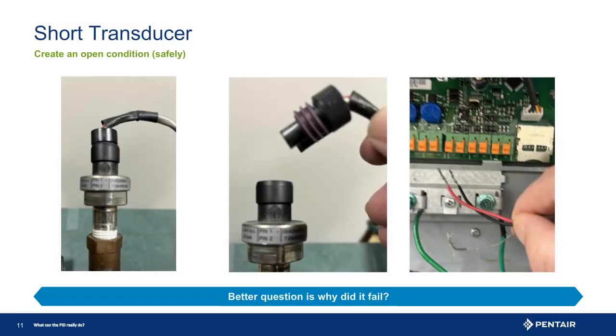Finally, what about a short transducer fault? Well, again, turn off the drive. Now unplug the transducer wire at the transducer and restart, then reset the drive. Run the drive. Does the fault change to open transducer? If yes, replace the transducer. If not, turn off the drive and remove the transducer wire at the drive.